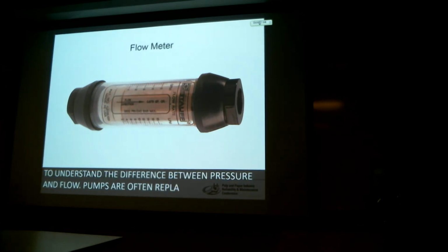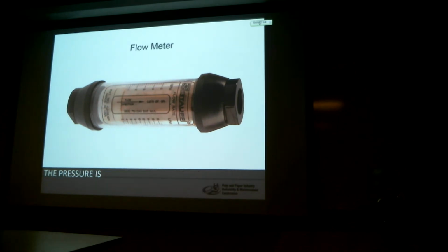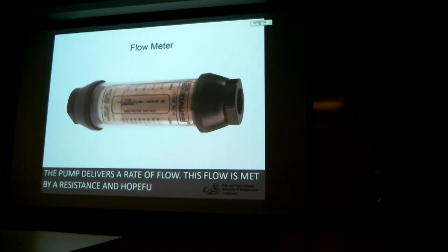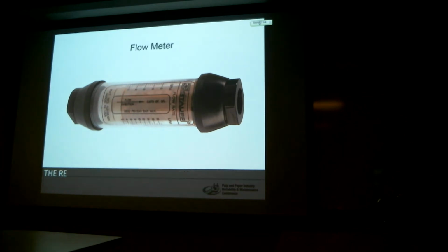Most people seem to think that a flow meter is unnecessary if there is a pressure gauge. We believe that this is the result of a failure to fully understand the difference between pressure and flow. Pumps are often replaced because the pressure is low. This is usually a mistake since the pump does not pump pressure. The pump delivers a rate of flow. This flow is met by a resistance and hopefully overcomes it. The result of this is pressure.